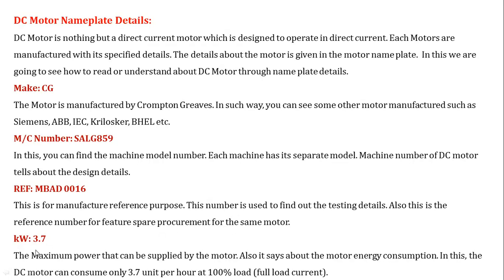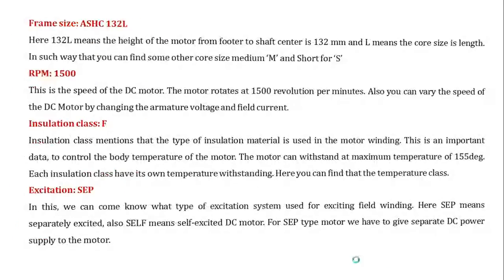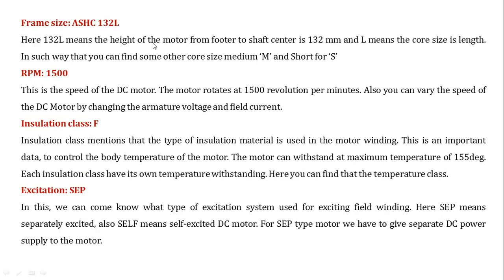Next one is kW, which stands for kilowatts. It tells us about the maximum power that can be supplied by the motor. Also, it indicates the motor's energy consumption. Next one, frame size. Here 132L means the height of the motor from the foot to the shaft center is 132 millimeters, and L means the core size is long. In such a way, you can find other core sizes such as medium or short. RPM is the speed of the motor.